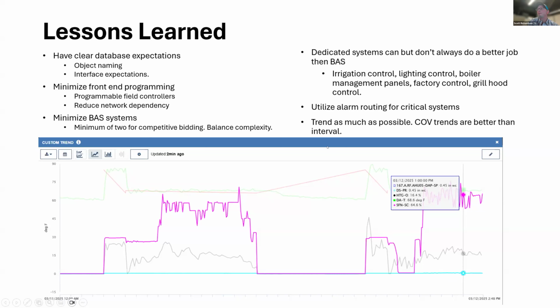My recommendation is to trend as much as possible and use COV trends, which stands for change of value. So when your input changes by a definable increment, you take a snapshot. That gives you the most resolution, and you're not wondering what happened in a 15-minute trend sample between two points. If it jumped and then leveled back out, you're going to see that jump with the COV trend.